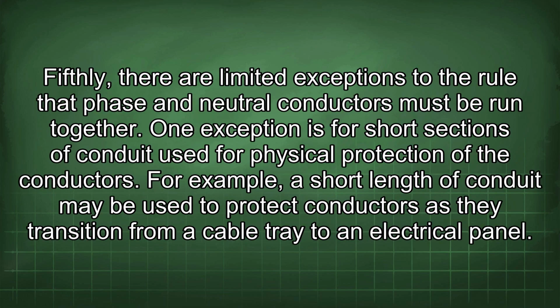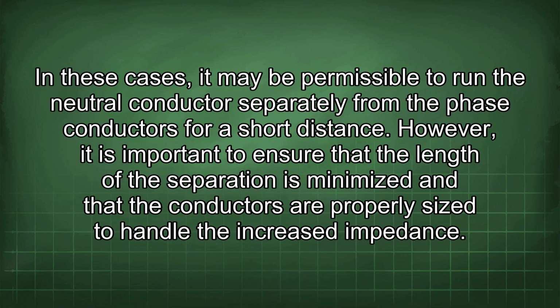Fifthly, there are limited exceptions to the rule that phase and neutral conductors must be run together. One exception is for short sections of conduit used for physical protection of the conductors. For example, a short length of conduit may be used to protect conductors as they transition from a cable tray to an electrical panel. In these cases, it may be permissible to run the neutral conductor separately from the phase conductors for a short distance. However, it is important to ensure that the length of the separation is minimized and that the conductors are properly sized to handle the increased impedance.